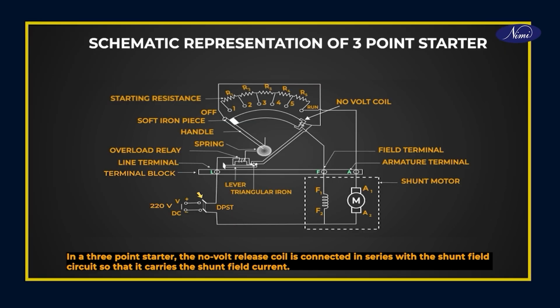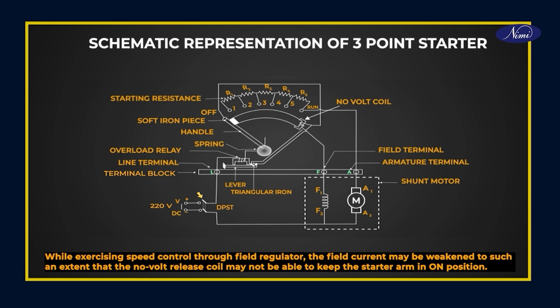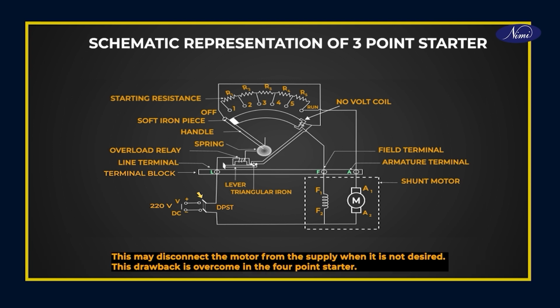In a 3-point starter, the no-volt release coil is connected in series with the shunt field circuit so that it carries the shunt field current. While exercising speed control through field regulator, the field current may be weakened to such an extent that the no-volt release coil may not be able to keep the starter arm in on position. This may disconnect the motor from the supply when it is not desired. This drawback is overcome in the 4-point starter.